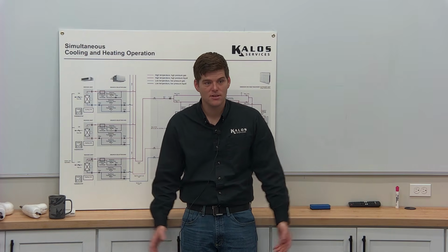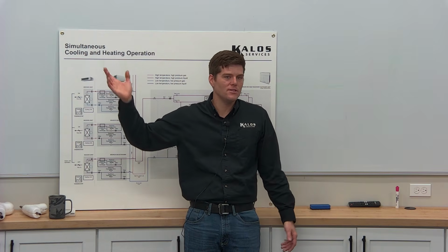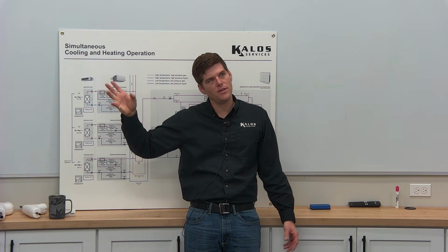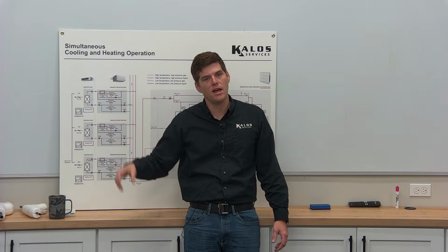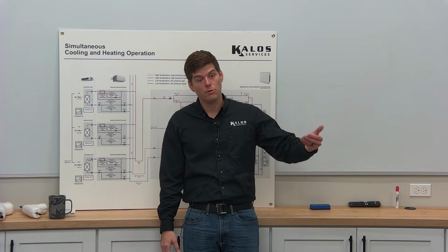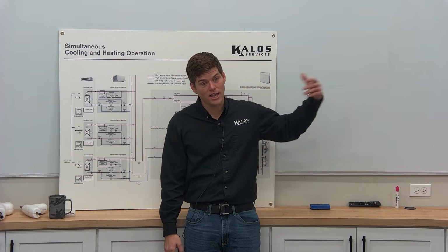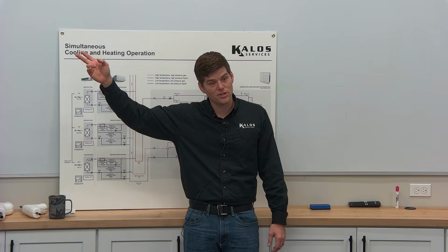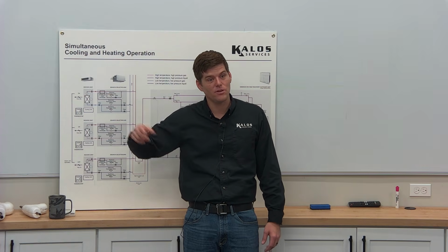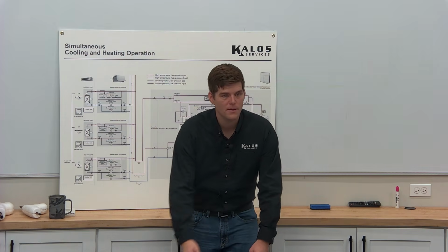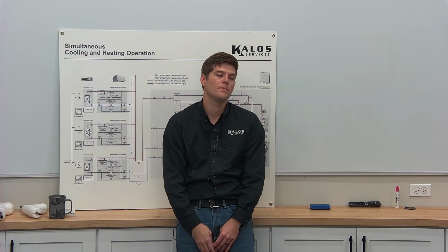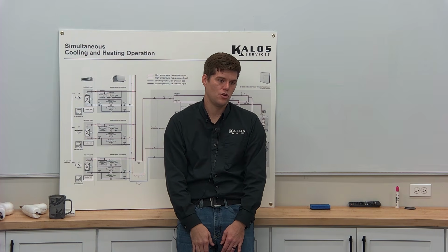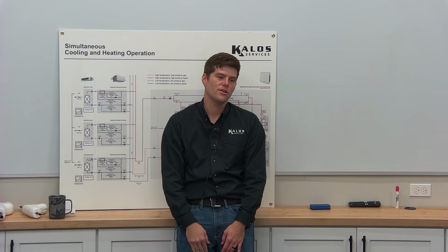And so the premise and the pitch behind this as to why this may be a superior system is that there is no chance that liquid refrigerant makes it back down the suction line to the outdoor unit, because they have the heat exchangers that are constantly changing hot gas to liquid. So there's that temperature exchange. You can have two units providing cold and one providing heating, for example. Correct. Because one is shooting hot gas.